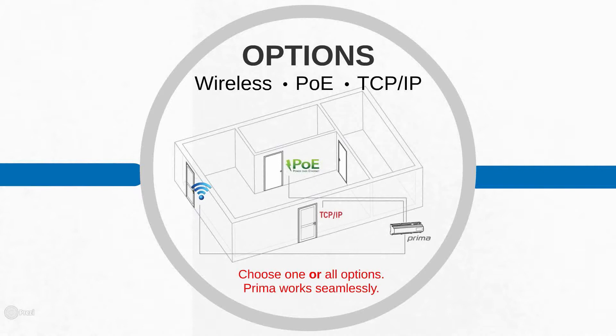One of the main reasons we went this route is that competitors who offer Wi-Fi create their own network through their controller, and when that network goes down, their systems stop functioning — you can't get in the door. Our system is a small Linux computer. If the network or Wi-Fi ever goes down — whether connected through hardwire, network cable, PoE, or wireless — our system continues to operate normally. Users will only know the network is down when they log into the web-based software, which will show centrals as offline. They won't be able to add people or update anything until the network is restored.